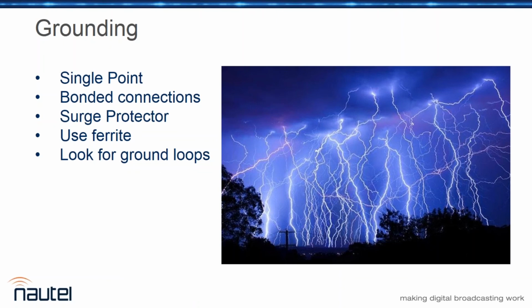We're not going to stop lightning, but we can, to some degree, control where it goes. It's a voltage divider theory, so we'll discuss that a little bit. We'll talk about the importance of bonding grounding connections as opposed to just folding two straps of copper over each other and hammering them flat. We'll talk about surge protection and the best way to install one. And it wouldn't be a presentation by Jeff if it didn't mention ferrites at least 4 times. So we'll talk about ferrites and how to track down ground loops, things like that. That's the basic stuff we want to look at with grounding.